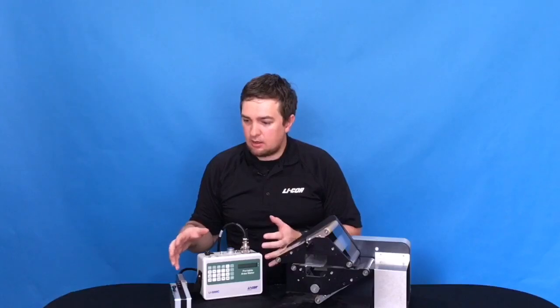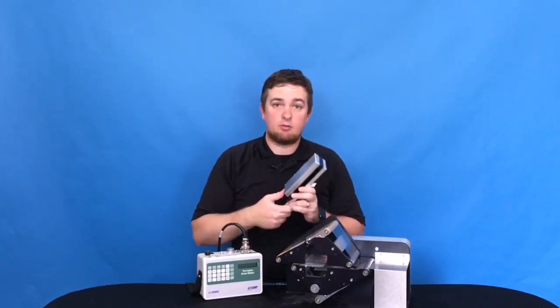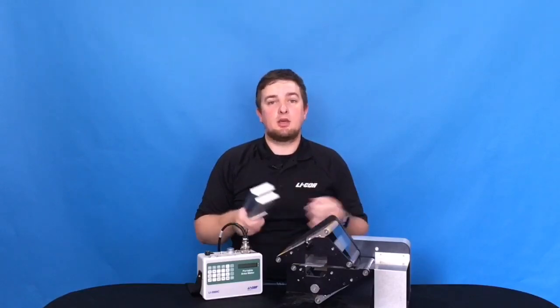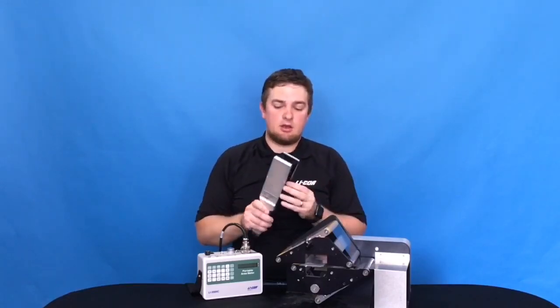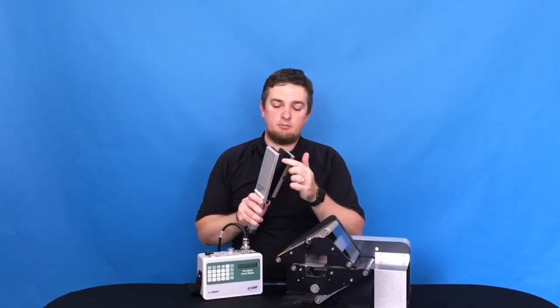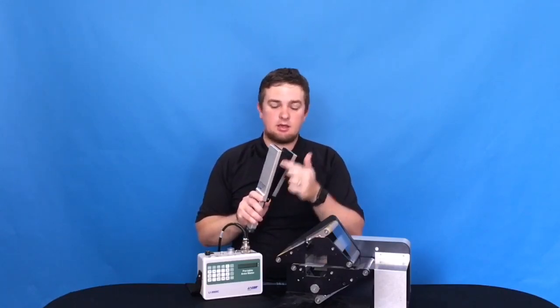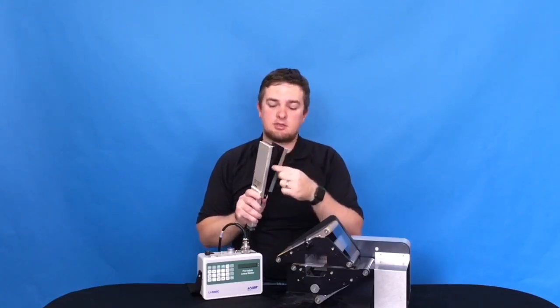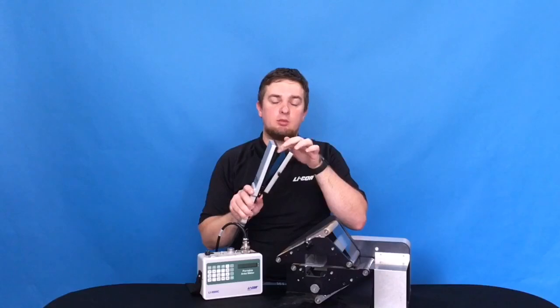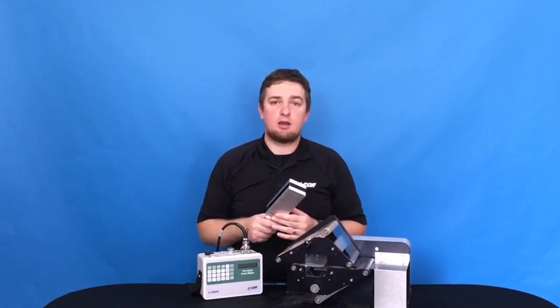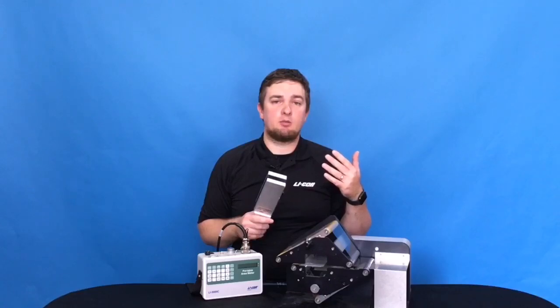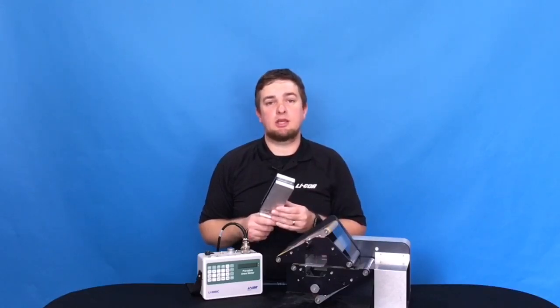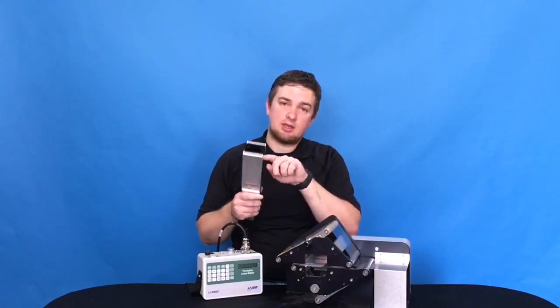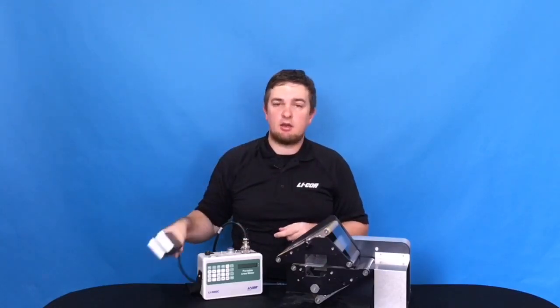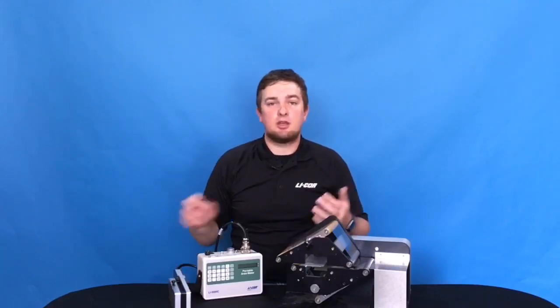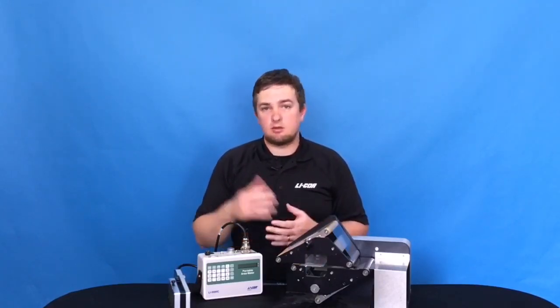As far as cleaning the instrument, the sensor head itself will make contact with a lot of leaves, and so it might get dust or dirt or pollen or sap or aphids all in the sensor head. So you should clean the detector side and the LED side of the sensor head, as well as this little flap in the middle. Just clean that with warm water and a damp towel, a paper towel, a cloth towel, something like that. You may need some cotton swabs to get into the corners, the very crevices of each of the edges, but generally you shouldn't need anything stronger than a damp cloth to clean that out occasionally.